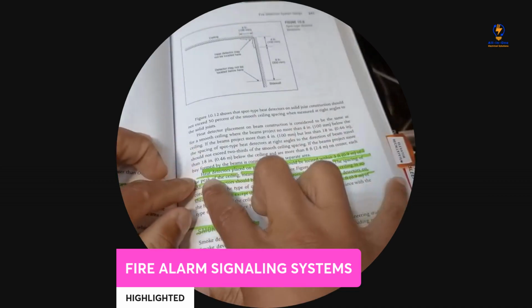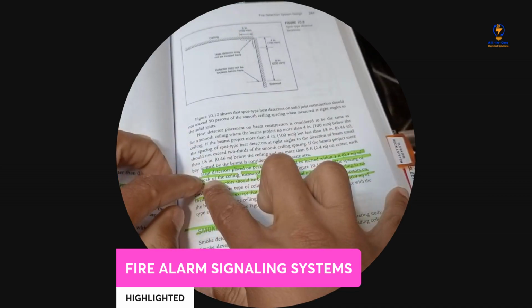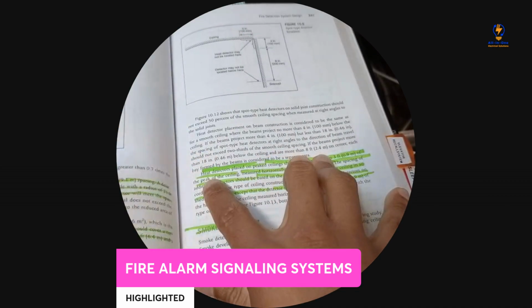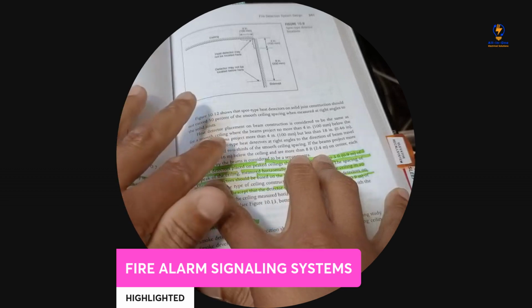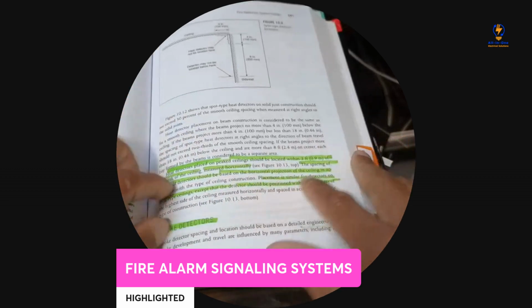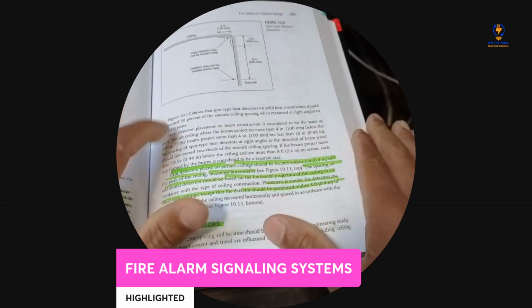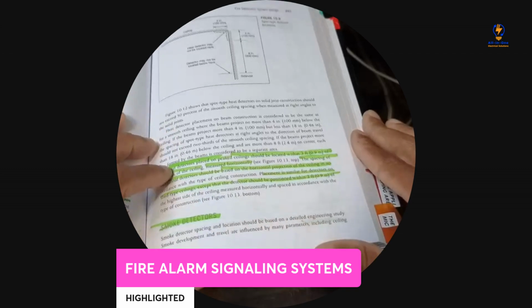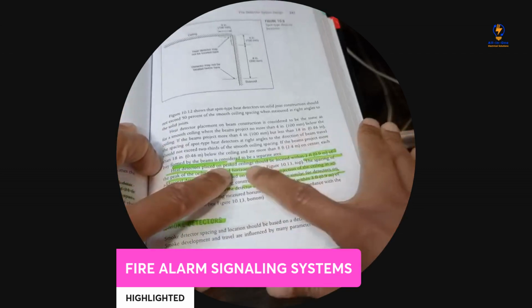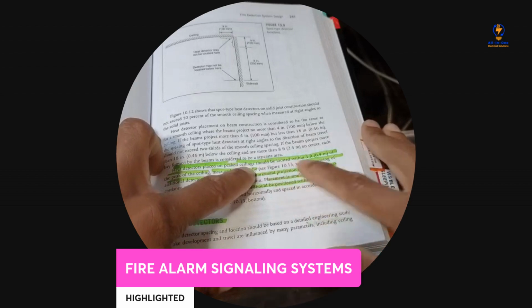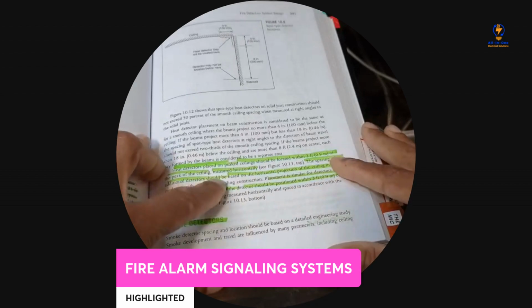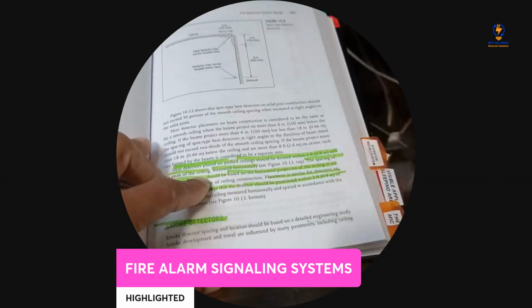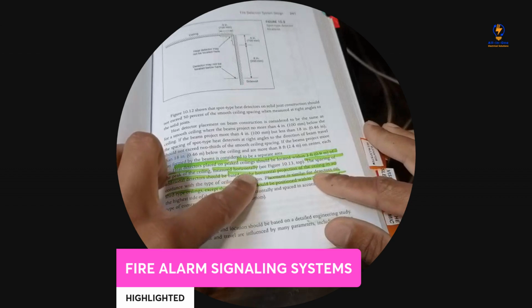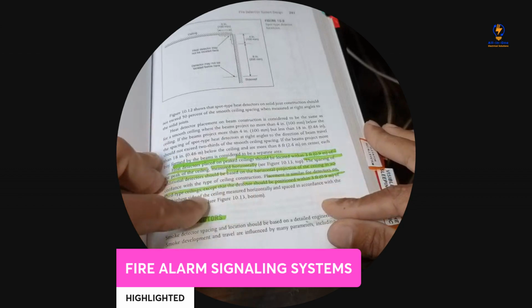As well here, on page 241, sorry, 241. We were on page 240. Now we are on page 241. Here, I think is the third paragraph right here. Third paragraph. Heat detectors placed on a peak ceiling should be located within 3 feet of the peak ceiling height, measured horizontal. Okay.